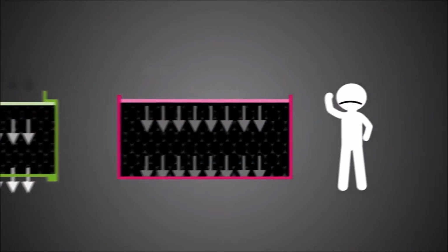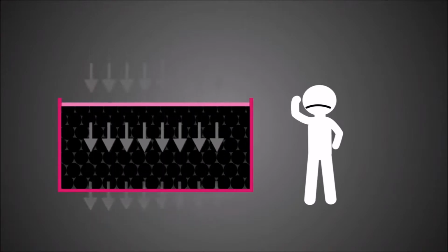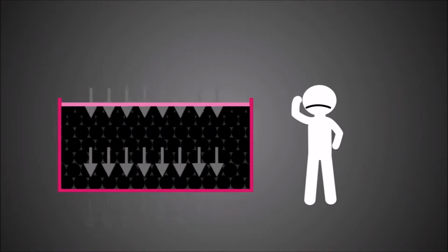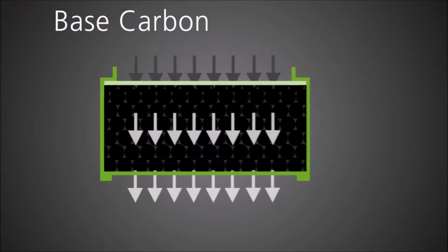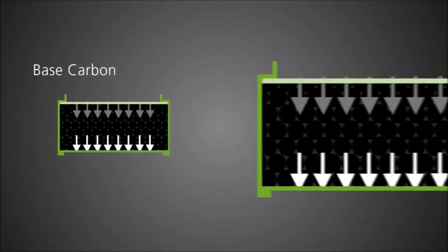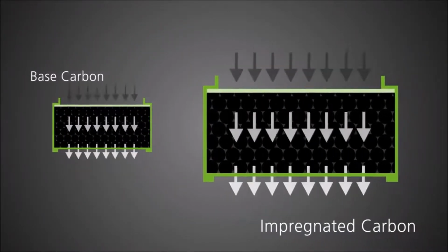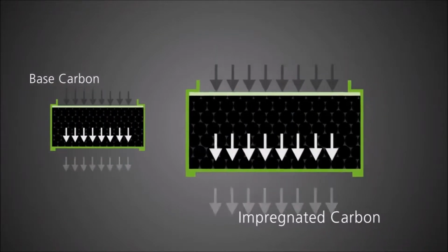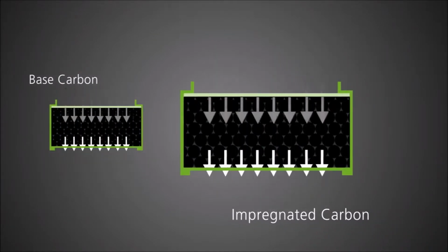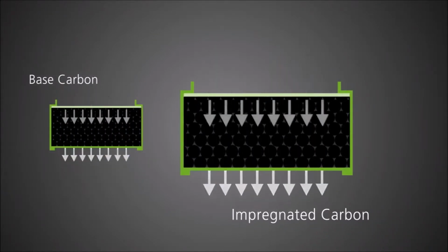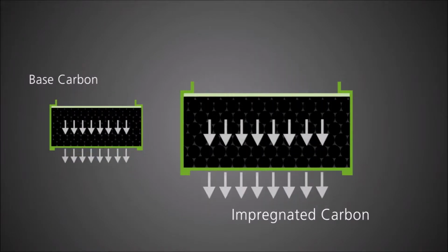There are fundamental requirements that have to be considered in the design and production of carbon filters. The surface area of the filter, coupled with filter depth and airflow, will give the required dwell time for both carbon-based and impregnated carbon filters. If these dwell times are not achieved, full adsorption may not take place and bypass will occur.